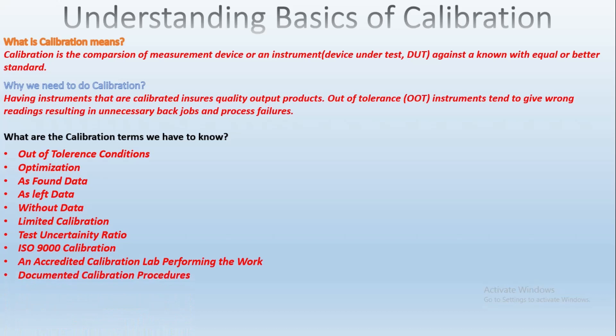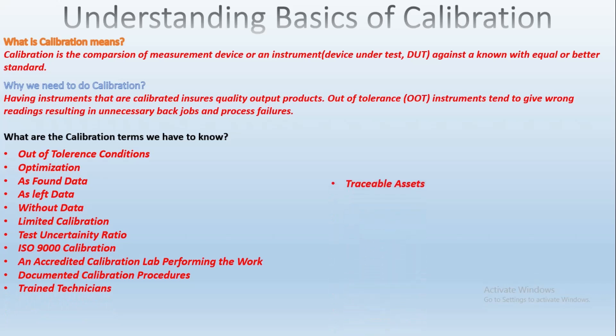Next is documented calibration processes — it is critical that a valid calibration procedure must be used based on the manufacturer's recommendations and covering all aspects of the instrument under test. Next is trained technicians — proper training must be documented for each discipline involved in performing the calibration.